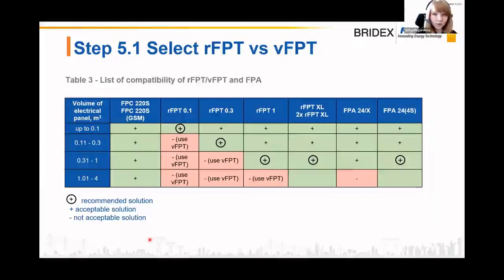Here is a list of compatibility of gas sticker, visual sticker, and gas sensor. There are different volumes of compartments. Gas stickers are also designed for different volumes. If the volume of the compartment is bigger than the volume of the gas sticker, and the cross section of bus bar or cable is small, use visual stickers. Single gas sensor FPA-24X is designed for volumes up to 1 cubic meters, and gas sensor FPA-24 with 4 coded sensors is designed for volumes from 1 to 4 cubic meters.